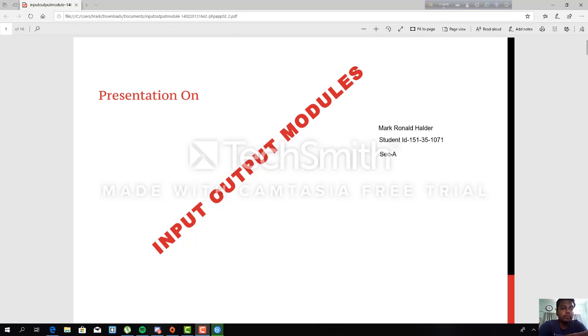Analog module configuration. Analog input information comes in as an input channel. Analog modules can be all inputs, all outputs, or a combination of input and output channels. Input word assignment: the 1746-NI8 is an 8-channel analog input module. 8 words will be assigned to the input status table as part of the I/O configuration. A module in slot 4 will have words I:4.0 through I:4.7, one for each channel.